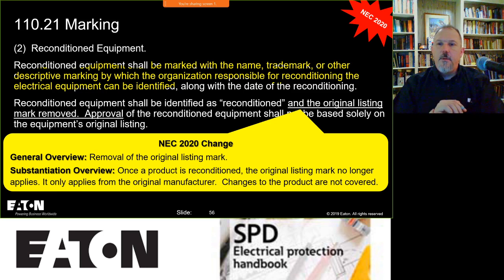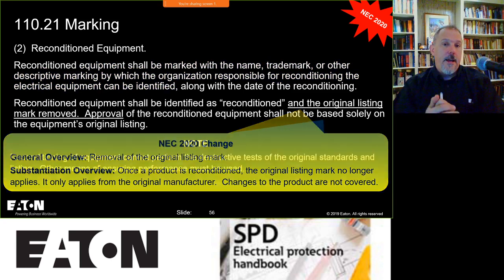I don't think an AHJ would push back if, instead of cutting a metal plate out of that nameplate, you cover it and make it so that old listing mark is no longer applicable. I've heard the term obliterate used, you know, mark it up, score it, or whatever. But in a lot of cases, when they work on those motors, they put a new label on it anyway, because some of those motors don't have the same horsepower rating that they had when they were old. So they change a lot of that.